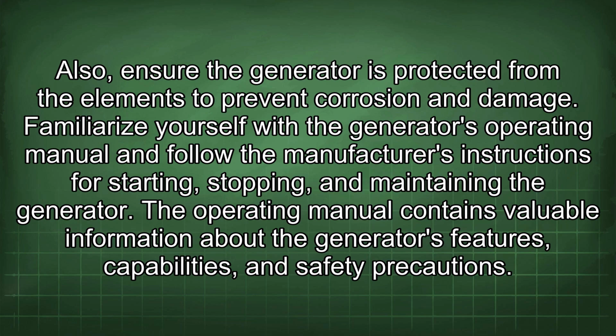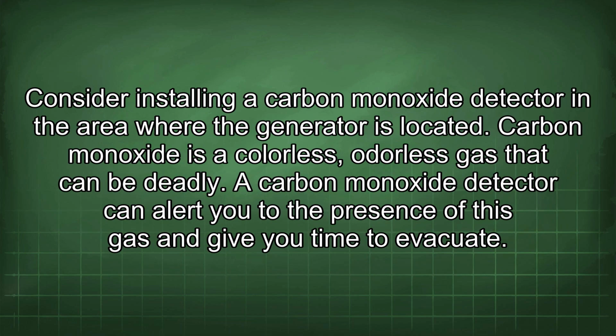Familiarize yourself with the generator's operating manual and follow the manufacturer's instructions for starting, stopping, and maintaining the generator. The operating manual contains valuable information about the generator's features, capabilities, and safety precautions. Consider installing a carbon monoxide detector in the area where the generator is located. Carbon monoxide is a colorless, odorless gas that can be deadly. A carbon monoxide detector can alert you to the presence of this gas and give you time to evacuate.